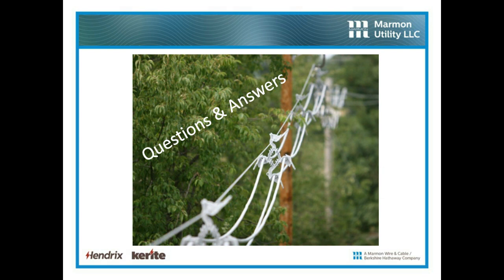So as I reduce the insulation wall, I will have, by definition, more surface current available. And eventually, yes, it wouldn't so much energize that tree unless that tree was completely wet. We've seen complete contact for years and never, quote unquote, energize the tree. But theoretically, could that cause a problem if I had fat tree branches rubbing on that tree for years? Yes, it could cause a problem.